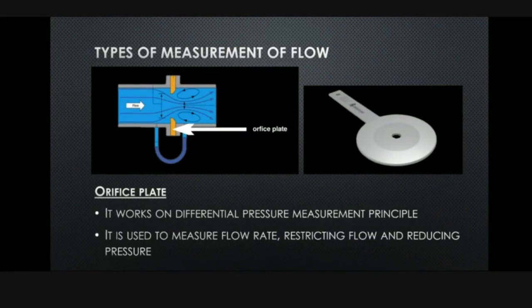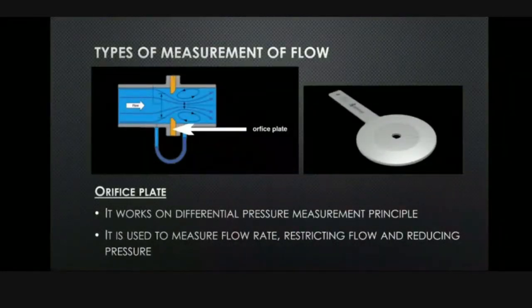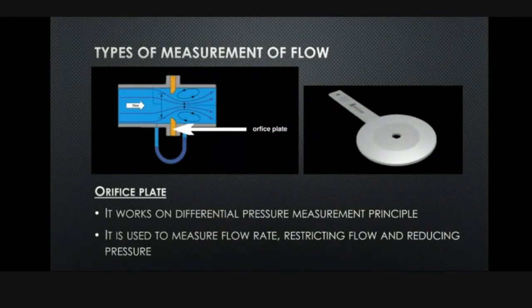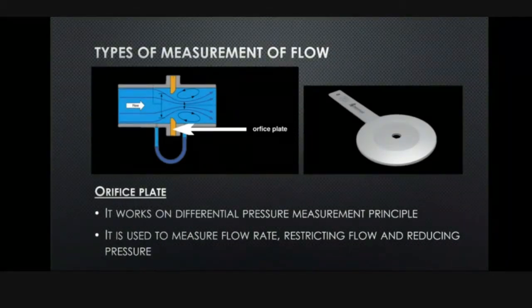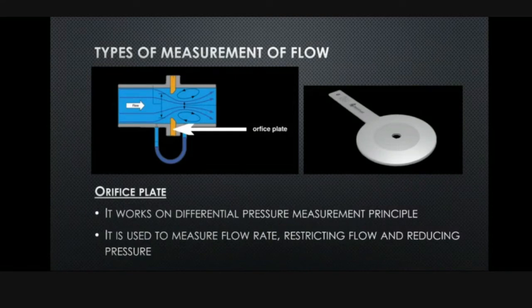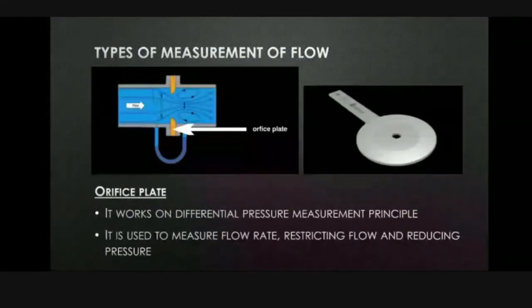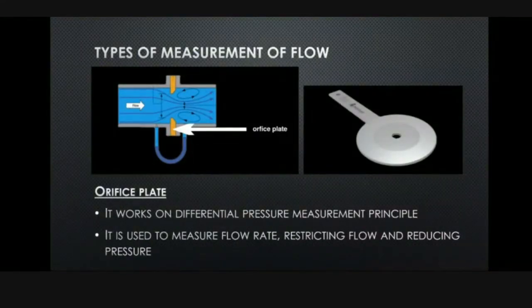And if we talk about working, the pressure builds in the upstream. First of all, the pressure builds in the upstream, which is on the left side of the orifice plate. When the pressure is built on the left side of the orifice plate, the fluid is converged and the fluid pressure decreases. The diameter of the orifice plate is at 45 degrees, so that the converged fluid will be diverged accordingly, and after the divergence, the velocity is reduced again, regaining its pressure.